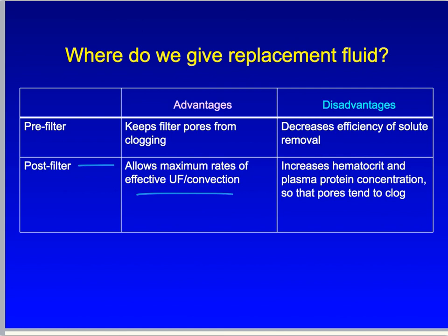But the problem with post-filter replacement is that pulling off large amounts of fluid by ultrafiltration increases the hematocrit and protein concentration of the remaining blood, leading to clogging of the hemofilter pores, which is made even worse by adsorption of protein molecules to the filter membrane. However, this problem can be partly counteracted by increasing the blood flow rate in the filter because the shear effect of blood flow tends to decrease protein adsorption.